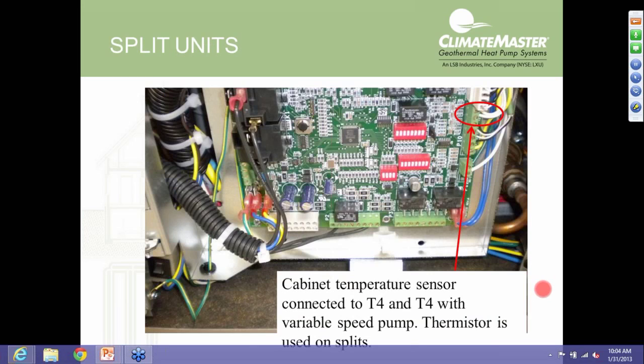On the split systems, we have an extra thermistor port, over here on the P10 connector that's circled, and we're using both T4 connect points, and we're actually using a thermistor instead of the bimetal switch. Because again, on the split systems, this port on the package units is actually the leaving air temperature sensor, but in the case of a split, that's actually then being wired to the AXM board up in the TAH air handler.